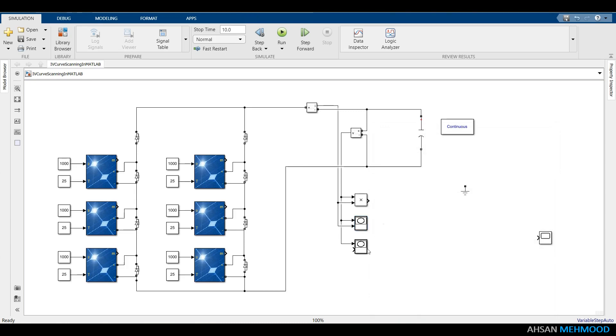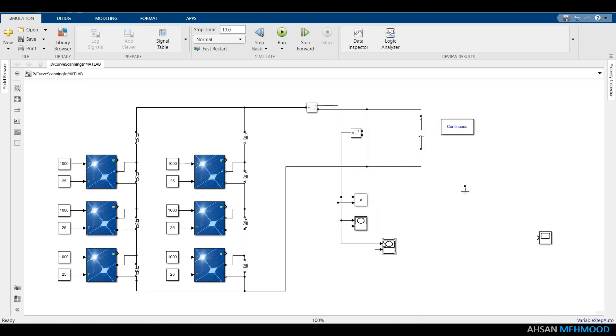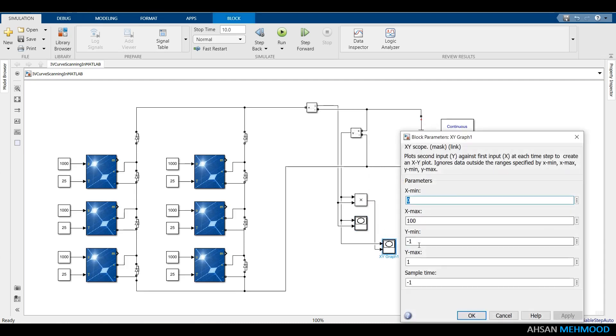Similarly, the Y-axis of the second XY graph block was chosen as array power. And its maximum limit was computed by multiplying the maximum power value of one PV module, by the total number of PV modules, that is 6.